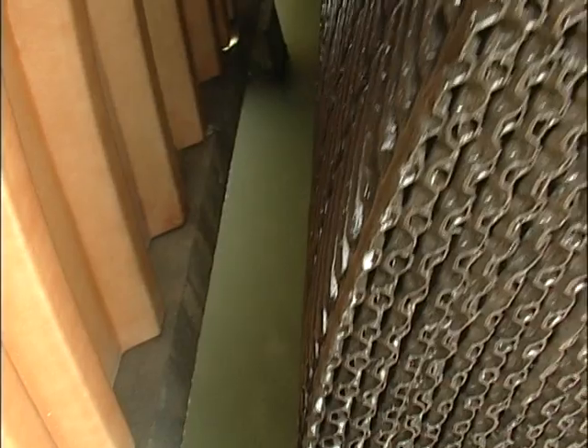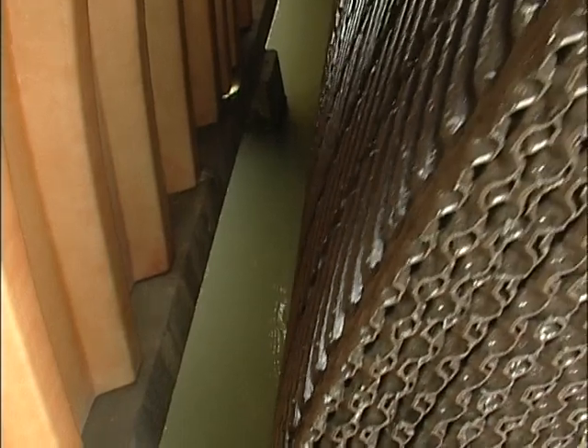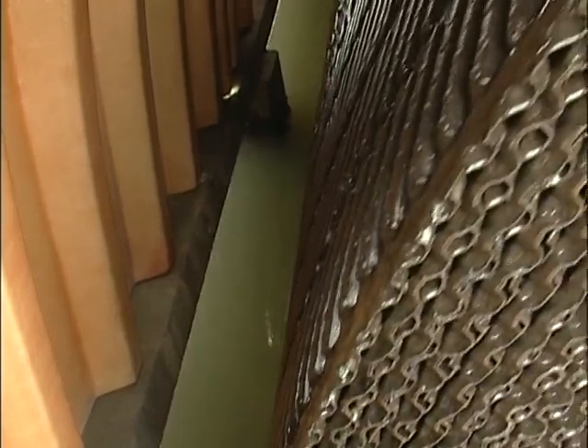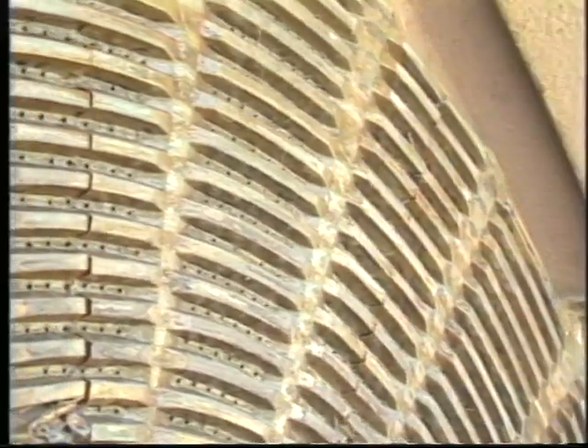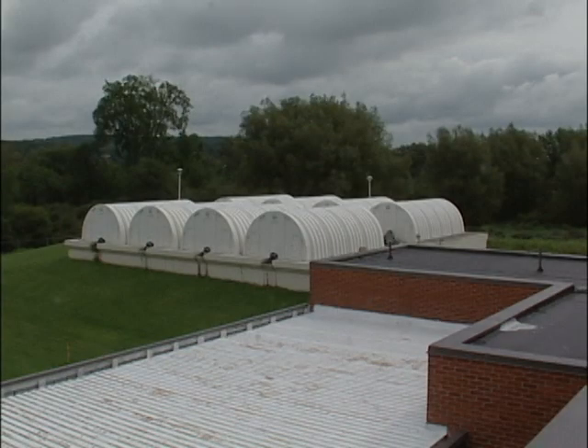RBCs utilize high-density plastic discs that are placed on shafts up to 25 feet long. These units are placed into a tank that usually submerges approximately 40% of the media in the wastewater. The media usually rotates at a speed of 1 or 2 RPMs. Most RBCs are covered to protect the biological growth and to protect the media from damaging ultraviolet rays.